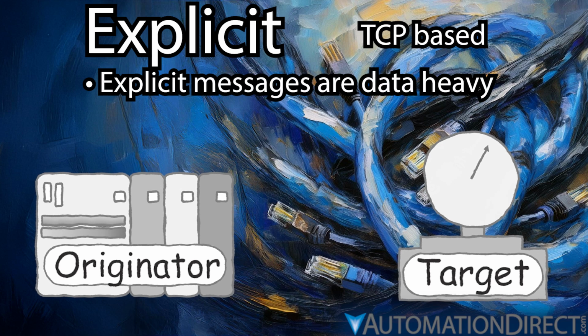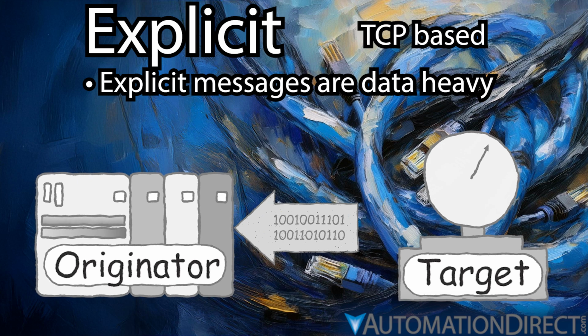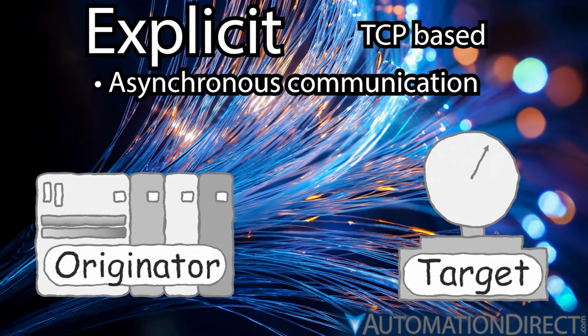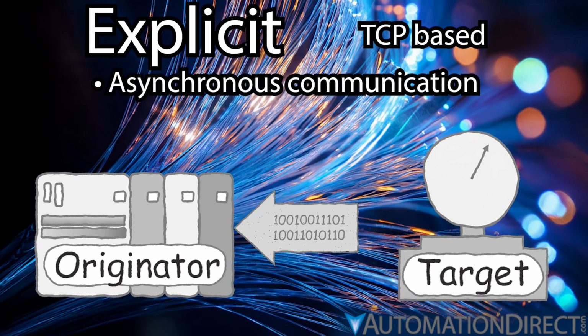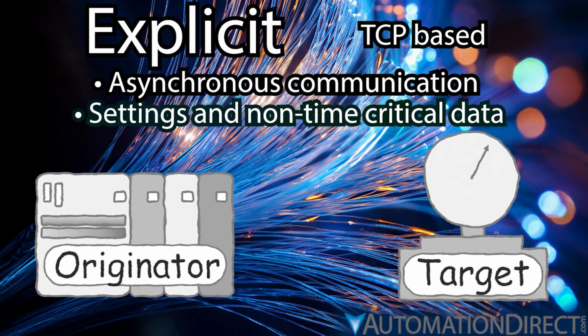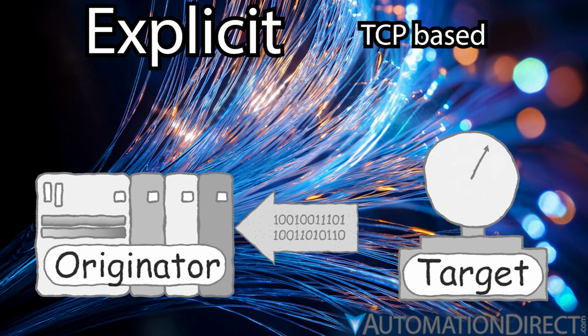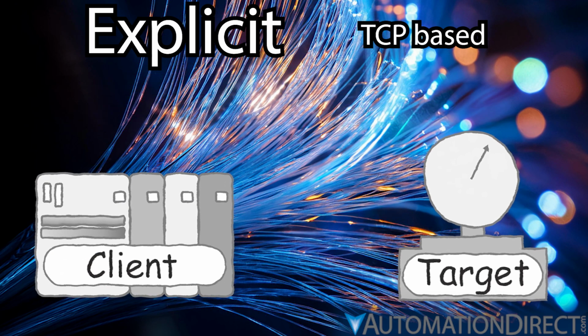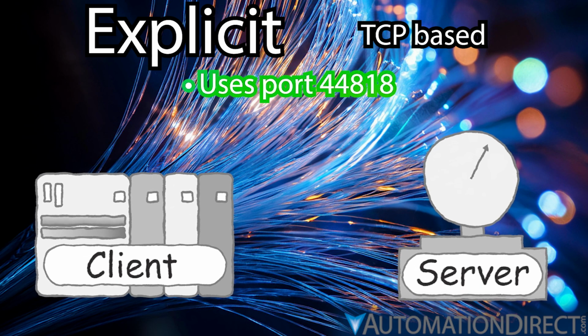The explicit message has a lot of overhead and carries a lot of data, so of course it is relatively slow. For this reason, explicit messages are sent asynchronously, only when required. They are often used to carry settings and other non-time-critical data. In explicit messaging, the originator is typically called the client, and the target is the server. Explicit messaging uses port 44818.